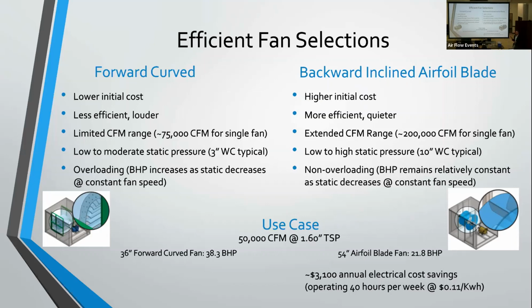Let's look quickly at efficient fan selections, specifically types: forward curve fans versus backward inclined fans, backward inclined airfoil blade fans specifically. Your forward curve fans are going to be at a lower initial cost, which is usually a good thing. But the problem is they're less efficient and they're louder compared to backward inclined airfoil blades. You're also limited on your CFM ranges with forward curve fans. Typically, on a single fan you can probably get up to about 75,000 CFM. That's kind of pushing the upper limit. They'll operate well at low to moderate static pressures, although you can run them at a higher pressure. I typically don't go over 3 to 3.5 inches on a forward curve fan because your brake horsepower goes through the roof, your noise goes through the roof. That's usually where I kind of draw the line. You can run them a little bit further, but 3.5 inches is where I try to make that cutoff.